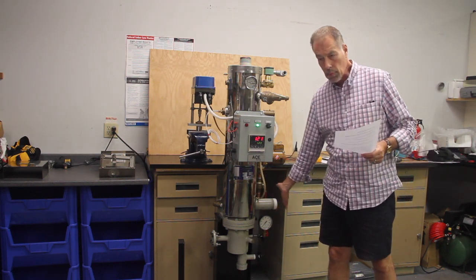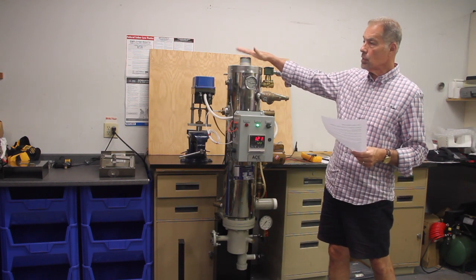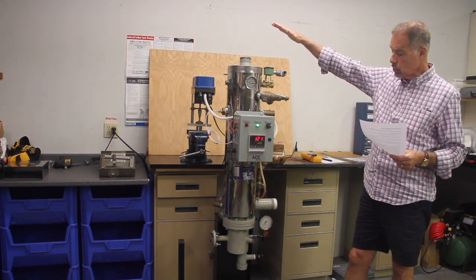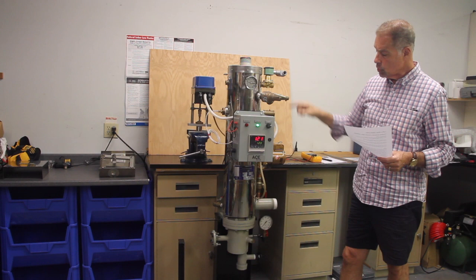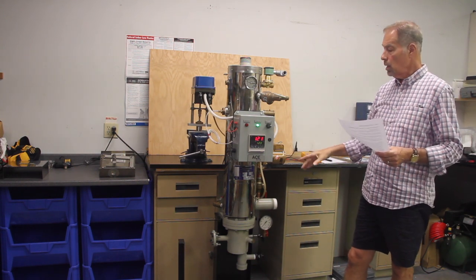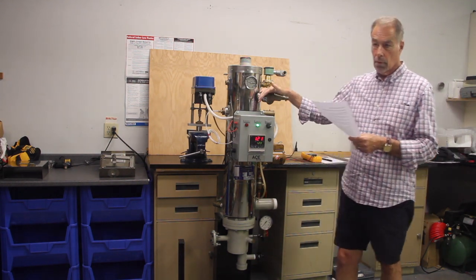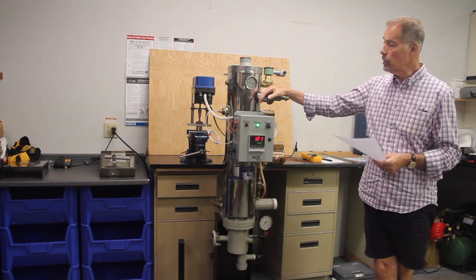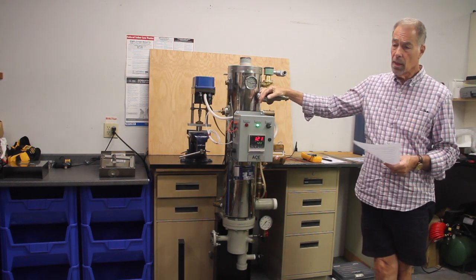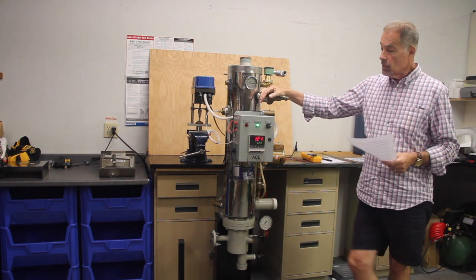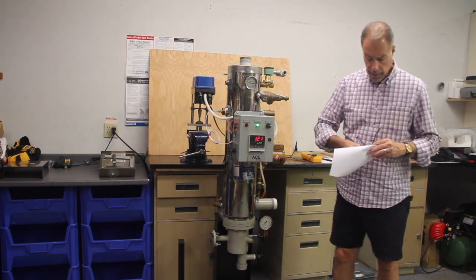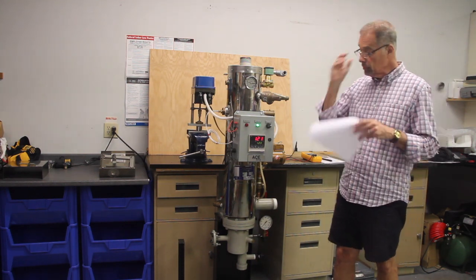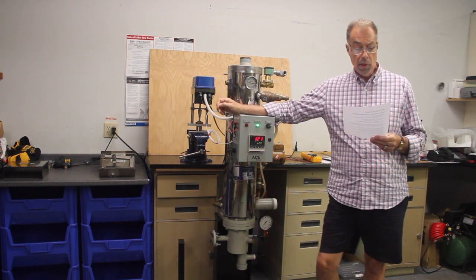Cold domestic water comes into this connection. Hot domestic water comes out of this connection. And it's basically a U-tube type heat exchanger in the shell. These can be offered either vertically, as you see here, or horizontal. They're made in several sizes. The sizes we sold at the Athletic Center, there's 3 heaters, 2 of which are for domestic water.